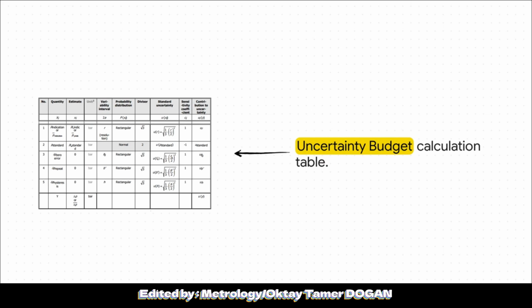You absolutely don't need to memorize the formulas here, but just think about the factors involved. You've got the resolution of the gauge, the standard uncertainty of your reference device, the zero error, repeatability, and hysteresis. The laboratory takes the standard deviation of all these separate variables, applies a rectangular or normal probability distribution, and then merges them all together, usually using a root-sum square calculation, to find the true, undeniable margin of error for that specific gauge. It's the whole shebang.